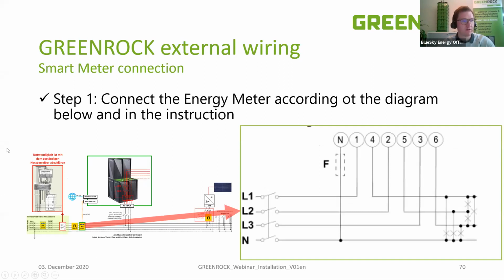So if you remember the schematic from a few slides before, this is the installation point of an energy meter. Really important that you use this point, and also really important that you use the correct measuring direction. So you see here, this means pin 1 of the energy meter is used coming from the grid, and pin 4 is used for going to the loads, to the system or wherever.